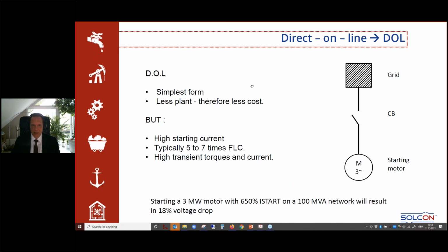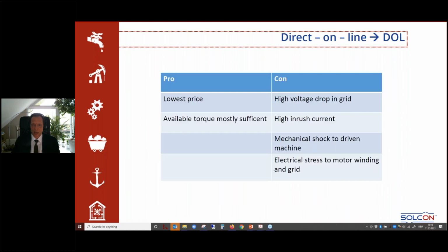Direct online, it's clear, is the simplest form, less cost, usually 5 to 7 times full load current. With this, you have high transient torques and current. For instance, if you have a network of 100 MVA minimum short circuit power, 6.5 starting current, 3 megawatt motor, this would result in an 18% voltage drop. Normally, customers do not accept this and want to have something done about it.